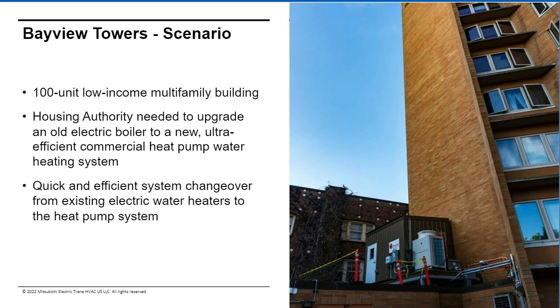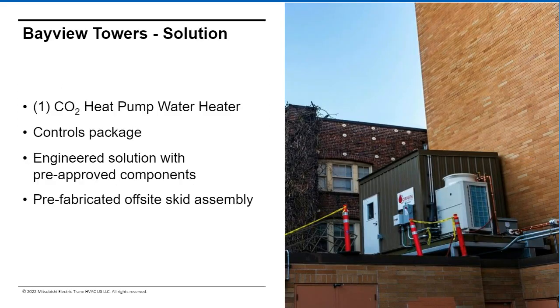And what we developed and went through with various industry partners is a method to add a QHV heat pump onto this project and include it as an easy changeover from their existing system. So this isn't necessarily an offering that we're promoting today, but is a solution we provided for this system. What this looks like is we had 1 heat pump, again, about a 10-ton heat pump. And then in this pre-manufactured offsite assembly, we had 3 storage tanks and pumps, heat exchangers, as well as our controls to control everything. Essentially it meant 2 water tie-ins to their existing hot water system.